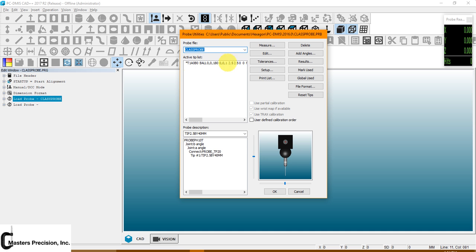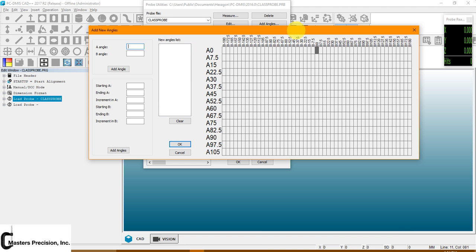As stated, we have the 0 angle already in. To add angles, I'm going to go over to where it says Add Angles. And I get this grid that comes up. Now this grid is not the easiest thing in the world to see. So what you're going to have to do at this point would be, let's say if we went A0, let's go A90, B0. I would just have to follow the 90 on over to where I get to the B0. And check this box in the grid, and it brings the tip in, A90, B0.